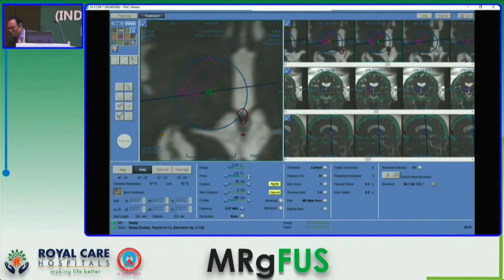Now you want 50 degrees, then we'll go up to 6500 joules. We'll double, sir, actually. Will it be very high? No, it won't be very high, sir. In fact, Raghu wants a little more. 8,000 joules. No, 7,500. We don't want more. Okay, 7,500 is what you want. So we fixed it at 7,500. So 7,650 joules, 10 seconds, and we'll see the clinical response on 850 watts. Yeah, we're going to sonicate now.